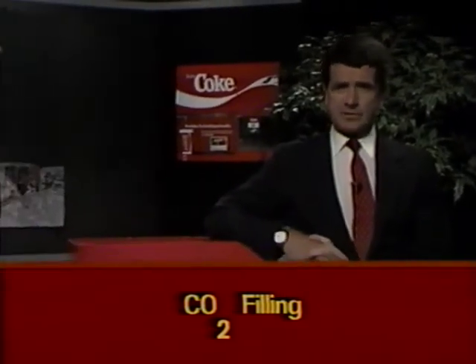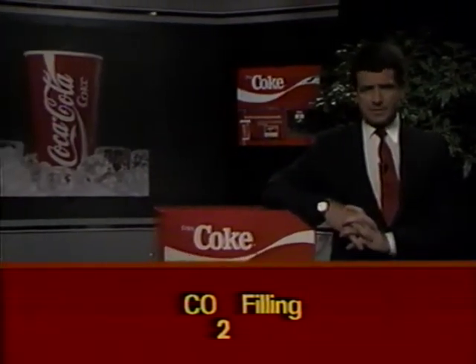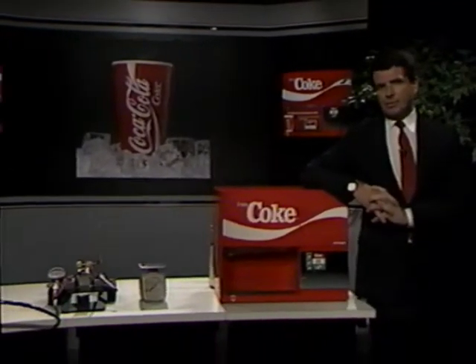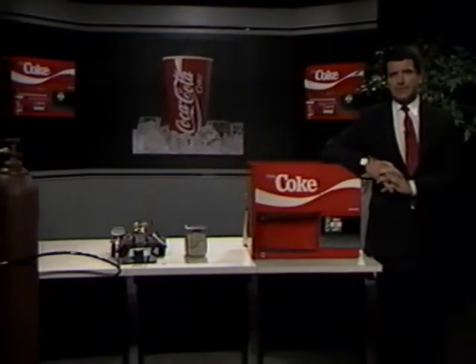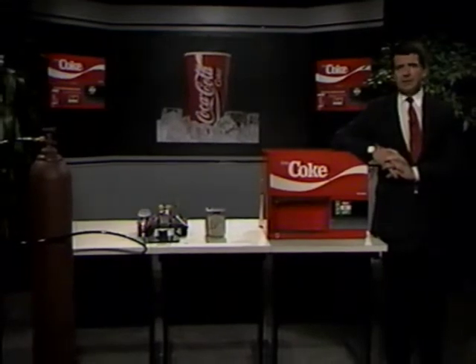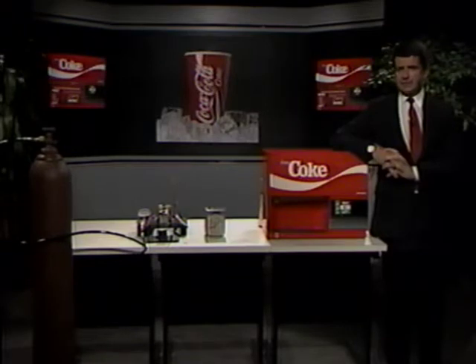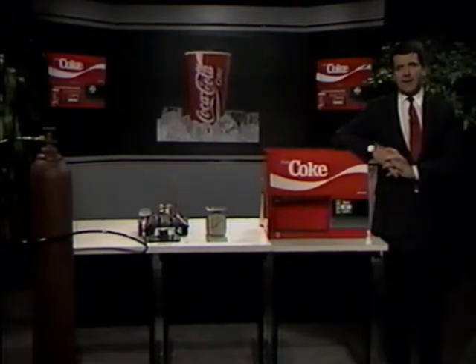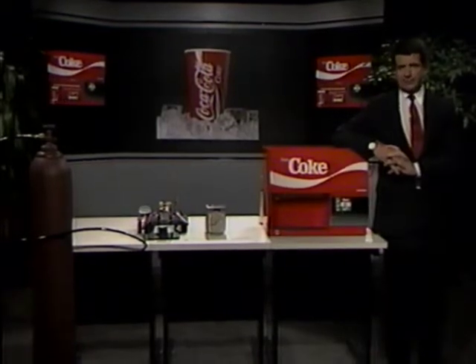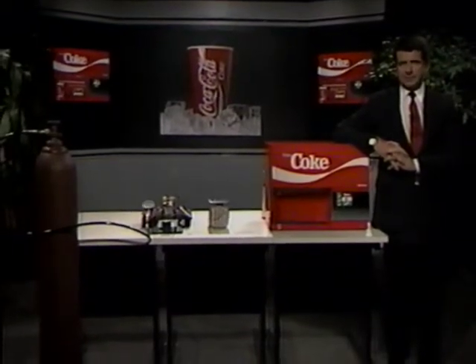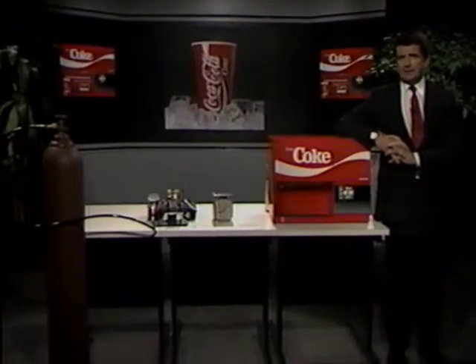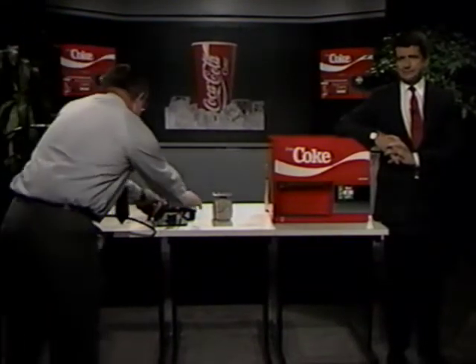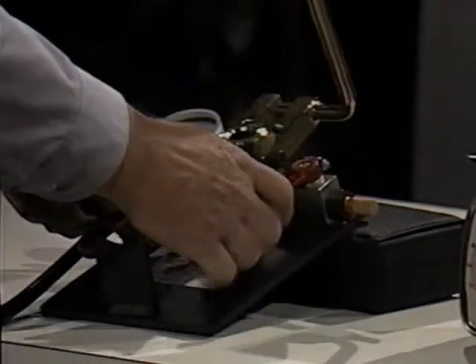There's one more basic we're set up to show you now. That's CO2 filling. To fill the 1 1/4 pound CO2 cylinders, you need a filling kit, a 50-pound CO2 cylinder with a dip tube, and a freezer for chilling the empty CO2 bottles in order to speed up the filling process. After attaching the CO2 line from the filling head to the 50-pound cylinder, close the inlet and vent valves at the filling head. Open the valve on the 50-pound cylinder.